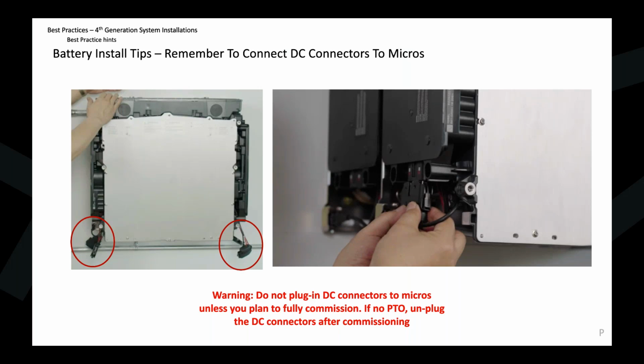We are working, Dennis, on being able to just use the AC Sense. The reason we don't now, and don't promote it, is because we don't have it UL listed - we didn't certify it that way. But we are looking at getting like a toggle or push button where we can utilize that AC Sense and not have to use that big 100 ampere, which obviously doesn't look great and costs money. As of right now it does require a 3-pole, and we do need to disconnect using that AC Sense, so more to come on that. I don't have an ETA on when that certification is going to be final, but we are working on it, Dennis, and we are aware of what you're saying.